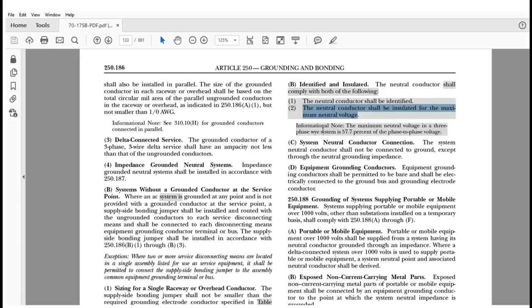The fine print note, excuse me, did I actually say that? The informational note that is added is significant to understanding if you're the electrician that's used to dealing with things like 2400 volt systems or 4160 volt systems or even higher, larger voltage systems. It says that 57.7% is the maximum neutral voltage, three-phase, for a Y system. It's between phase-to-phase voltage. So for example, if I had a 4160 volt system, 57.7% of the phase-to-phase voltage equals 2400 volts. So I have to make sure that my insulation is rated for 2400 volts, okay?